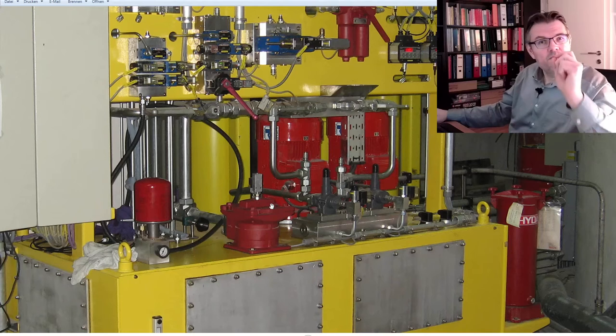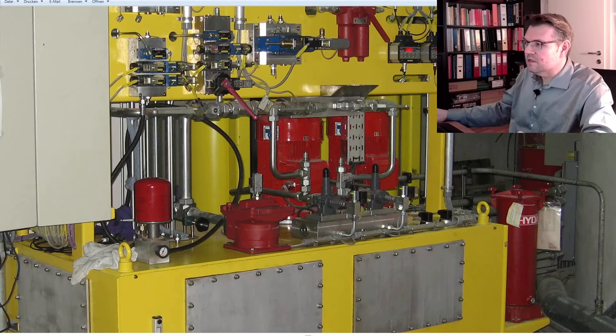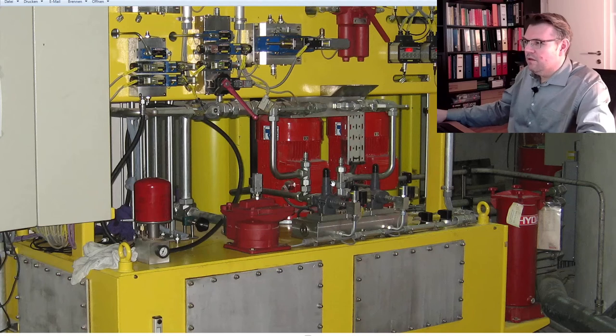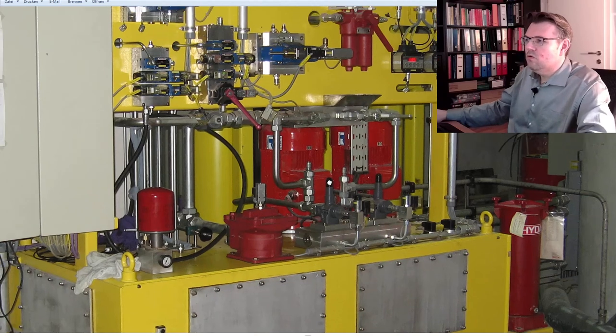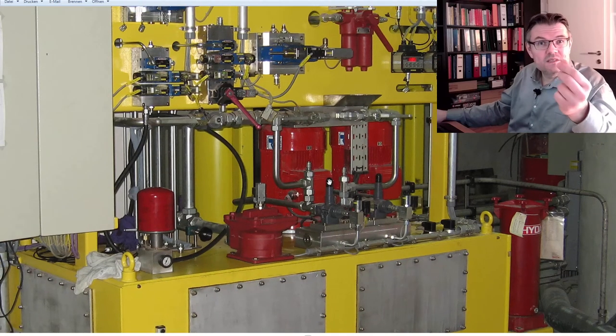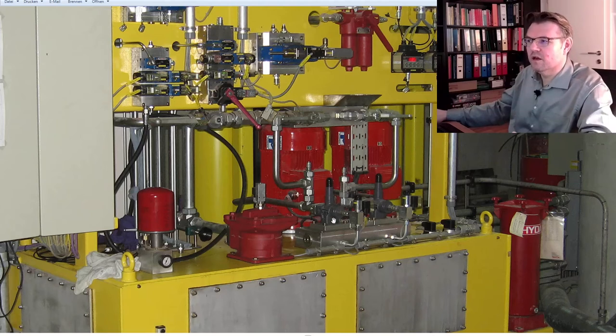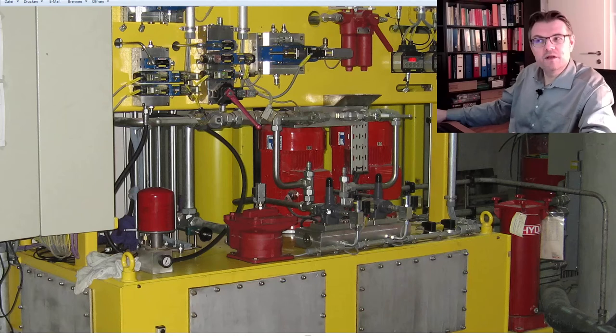Okay, so these are the two pumps. I always said there must be somewhere a pressure relief valve. These are these things here. You see here is the pressure coming. And under this black hood, under this black cap, there you can adjust the spring. This is how this pressure relief valve looks like. One for this pump and one for the other pump.